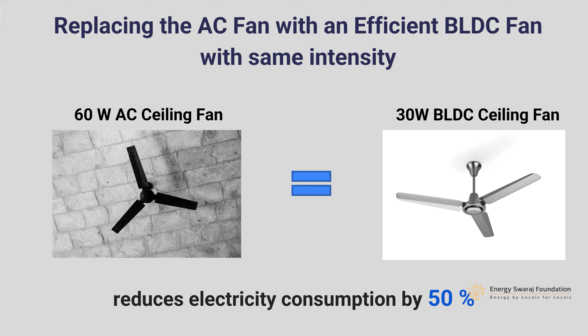You can replace the normal AC fan with the BLDC fan. The current fans that we are using actually use an induction motor, and there are more advanced new fans available with the BLDC motor, brushless DC motors. And what is the advantage? This brushless DC motor takes almost half or less than half of the power to run a fan of the same size with the same speed. So when you replace a normal 60 watt AC fan with a 25 to 30 watt BLDC fan, you are going to save more than 50% of the power, and therefore reduce your electricity consumption by another 50%.